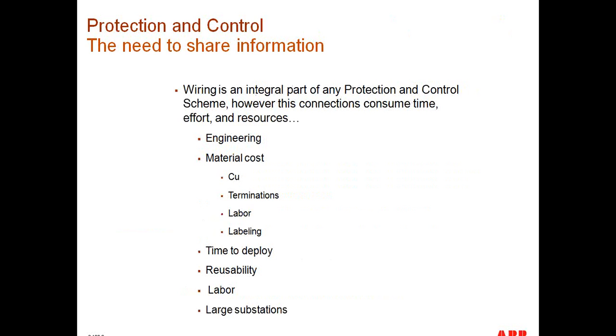So as we could see, just going through this array of conditions, wiring is an integral part of any protection control scheme. However, these connections consume time, effort, and resources, and for the most part, standards are developed at the end user level to facilitate the reuse of this engineering, but sometimes that particular scheme is not going to fit on all of the stations that require a breaker fail scheme.